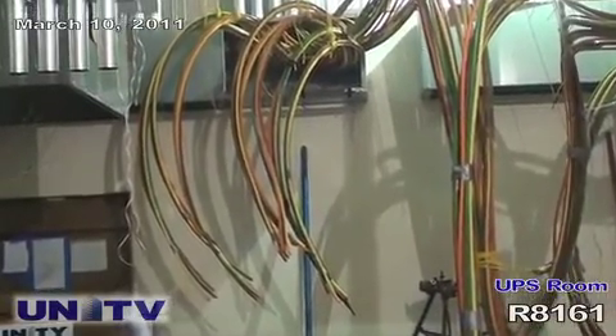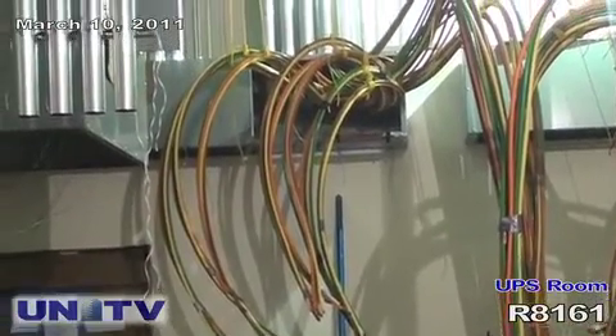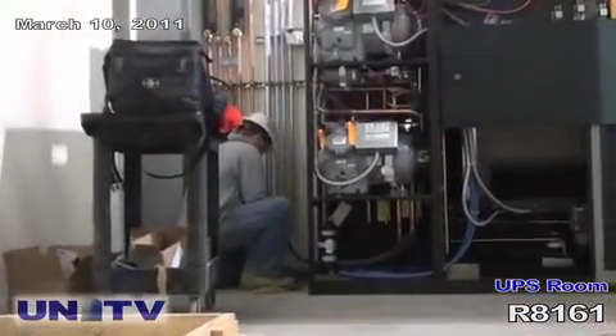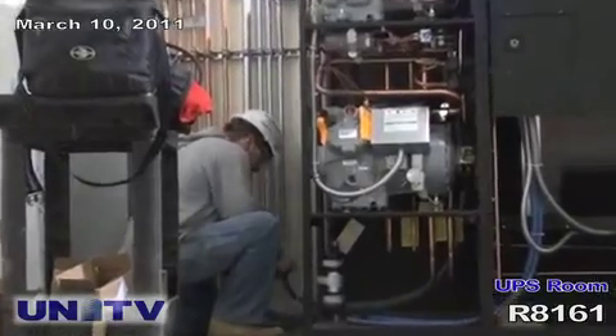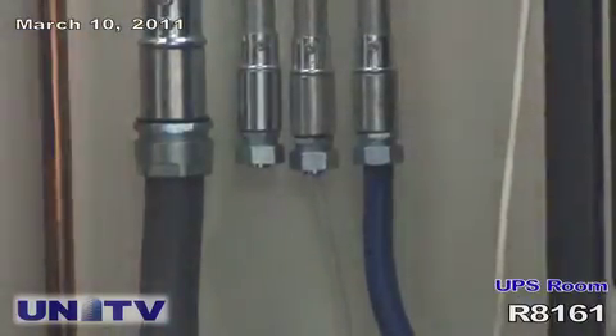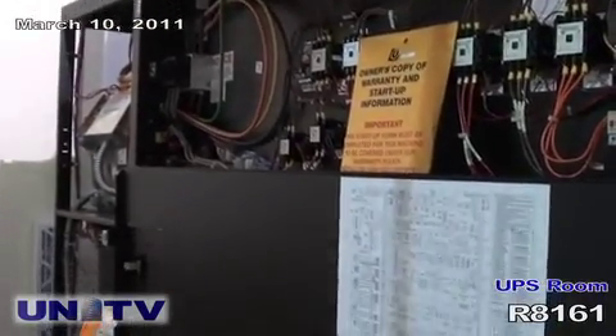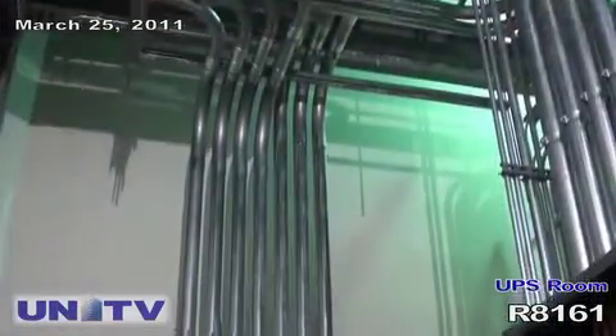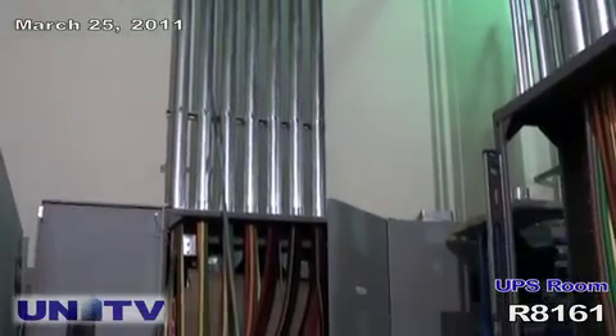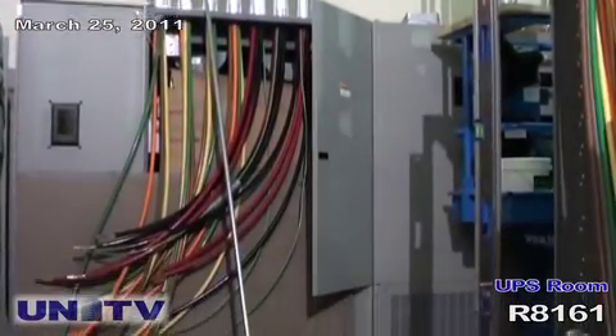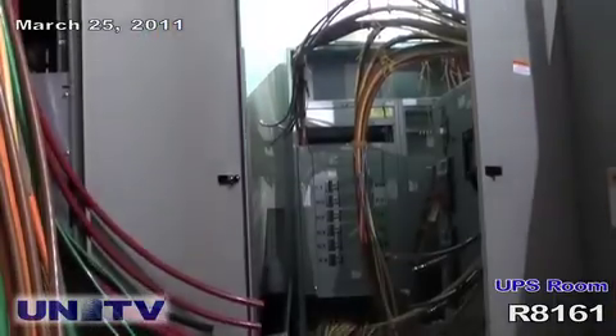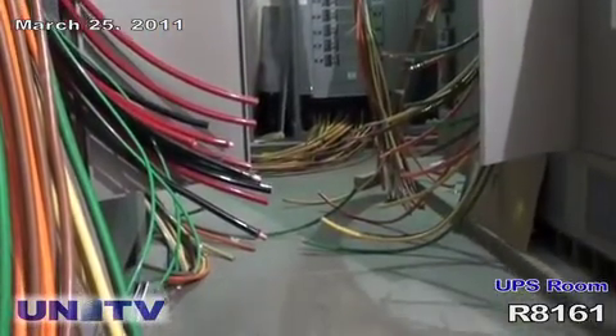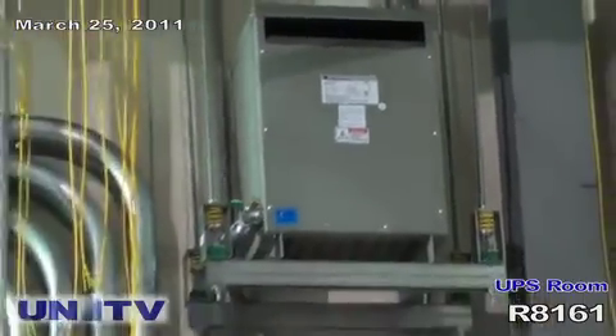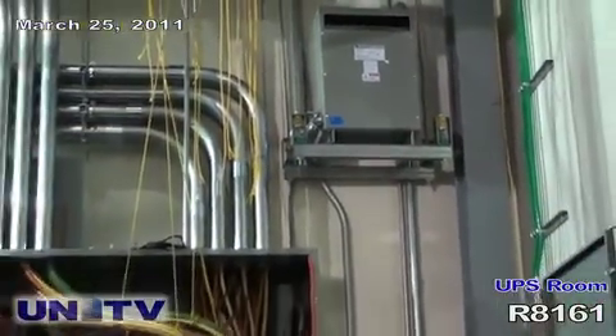UPS room. We put crowns in the air so we can run our conduit before the gear shows up. Here we're bringing in feeds, we're bringing in fire alarm and site scan to monitor the CRAC units. Here's a UPS. You can see the 480, plus you can see the DC, the black and the red, for the DC going to the battery racks. There's a critical distribution transformer that feeds all our fire alarm security.